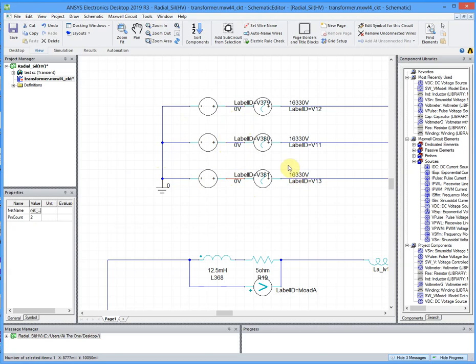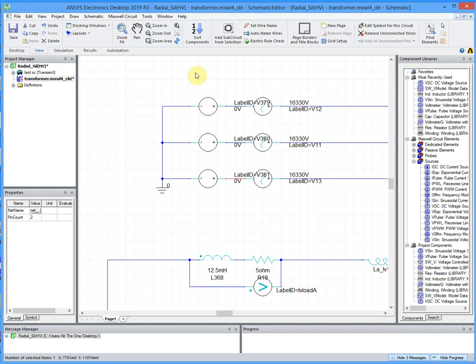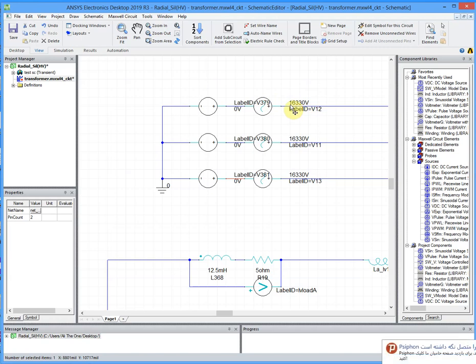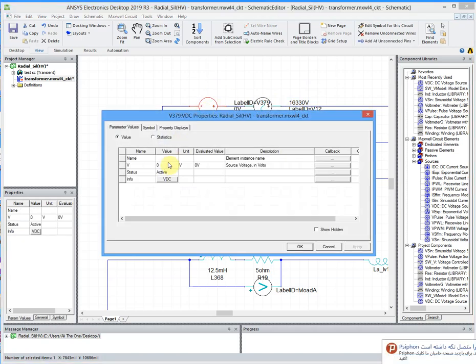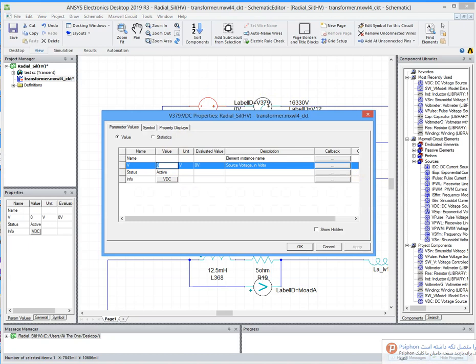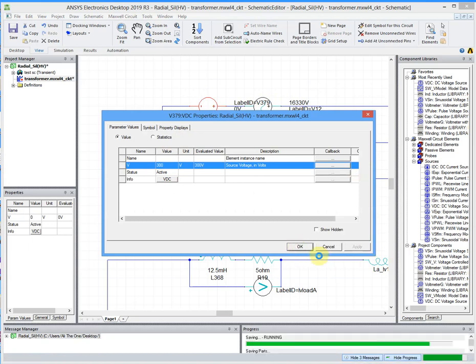As you see, the phase voltage of each high voltage winding is 16,300 volts. So we want to add some DC voltage to analyze the saturation by the DC voltage. The voltage is about 15,000 volts. Let's add, for example, 300 DC volts here.